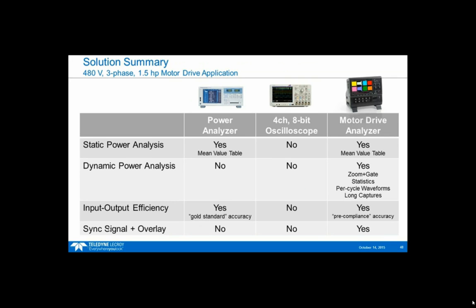We also showed the sync signal and the overlay. That's very nice - it allows us to verify that our setup is correct for period calculation for all the power values. That's very, very important when you have a dynamic event, because there can be a lot of things changing over time.